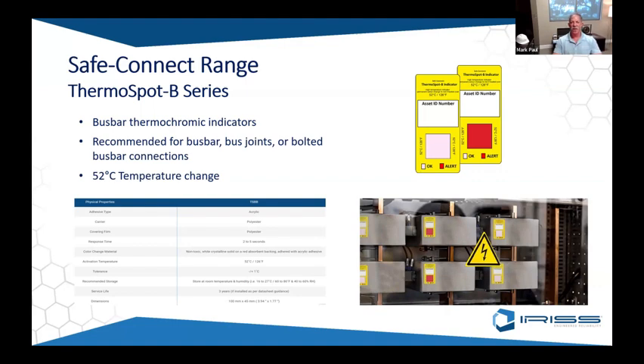Other applications these thermochromics are utilized in are bigger applications, or a different form, really, where we're talking about bus bars, bus joints, bolted bus bar connections. These are set at 52 degrees Celsius, a lower set point than the thermo wraps or thermal clips, because you would not want a bus bar or bus joint to get anywhere close to 70 degrees Celsius. So these indicate a lower temperature, more appropriate for what would be known as a fault condition in one of these applications. These stickers apply to any of those devices and quickly give a visual indication that there's an issue.